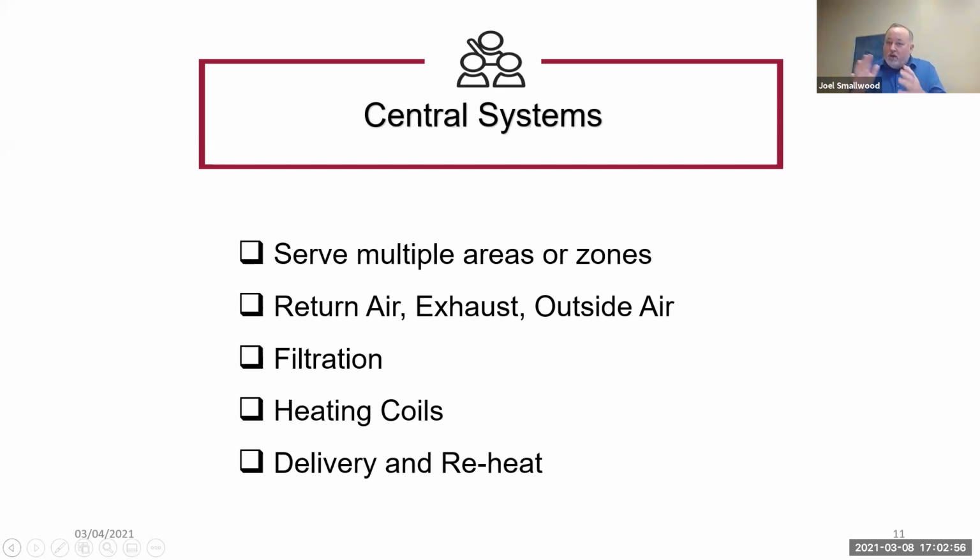So we have to monitor and regulate that. And these systems, that's part of what they watch all the time: what's the outside air temperature, what's the temperature inside this unit, to protect themselves from that catastrophic damage. So it is definitely a balancing, but the idea is that we bring in as much outside air as we possibly can, protect the systems, and keep the rooms up to temperature all at the same time. Bit of a balancing act there, Mike.